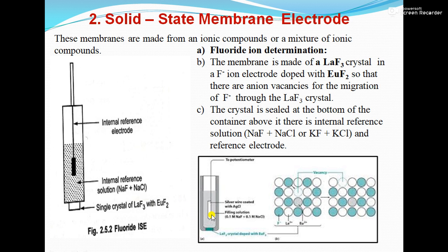So there is a difference in the concentration which is recorded by this wire. So you can see the crystal is sealed at the bottom of the container. Above it there is an internal reference solution that is of NaF plus NaCl or KF plus KCl and the reference electrode which I have already mentioned.